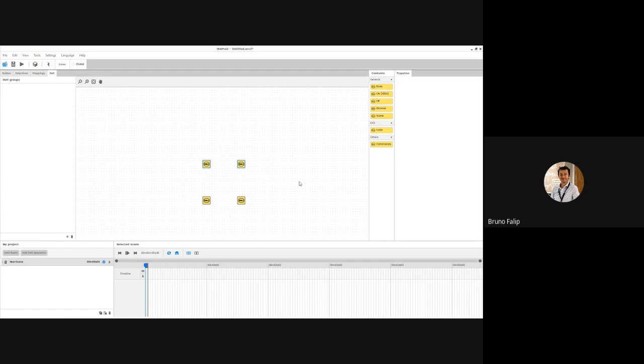This is something that is going to be released soon, but at the moment it's a single master only. Which means that, for example, you're not allowed to put another touch panel or sensor or whatever on the DALI bus in order to assign it to any lighting scenes. In future, there will be the possibility to do it.